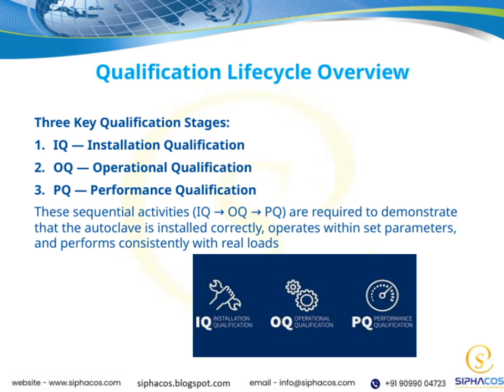This process is composed of 3 key qualification stages that are essential for ensuring the autoclave functions properly and reliably. First, we have the IQ, which stands for Installation Qualification. This stage confirms that the autoclave has been installed correctly according to all specifications and requirements. Next is the OQ, or Operational Qualification, where we verify that the autoclave operates within the set parameters under normal operating conditions. Finally, we have the PQ, Performance Qualification. This phase assesses whether the autoclave can consistently perform with actual loads, ensuring it meets the necessary performance standards over time. These 3 stages follow a sequence: IQ, then OQ, and finally PQ, and together they demonstrate that the autoclave is installed properly, operates correctly, and delivers consistent results. This structured approach is crucial for quality assurance and compliance in our sterilization processes.